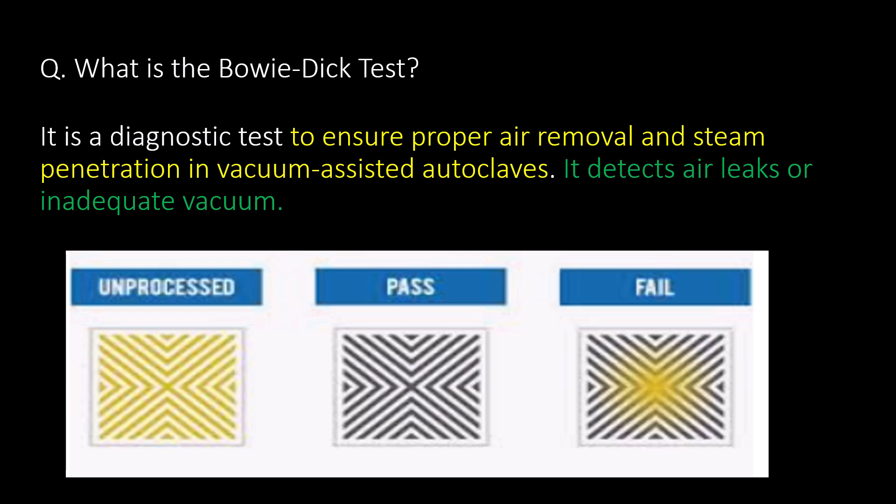What is the Bowie-Dick test? It is a diagnostic test to ensure proper air removal and steam penetration in vacuum-assisted autoclaves. It detects air leaks or inadequate vacuum.